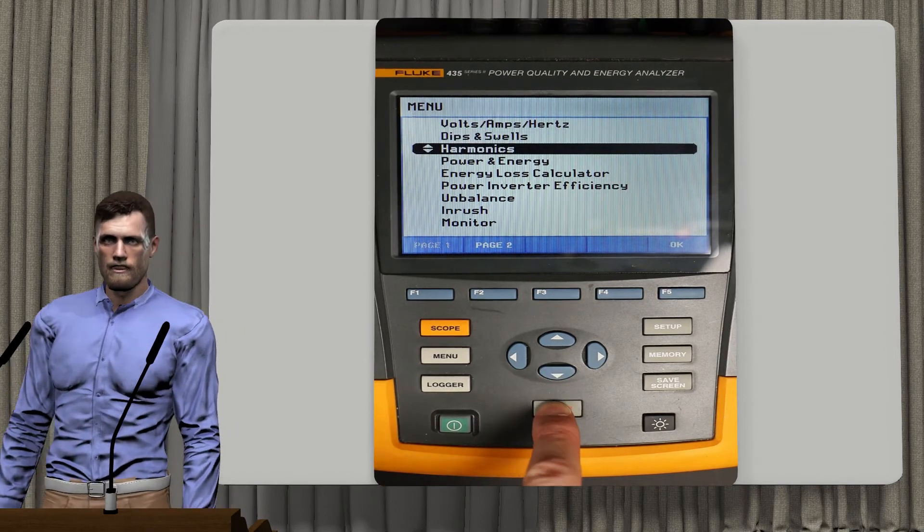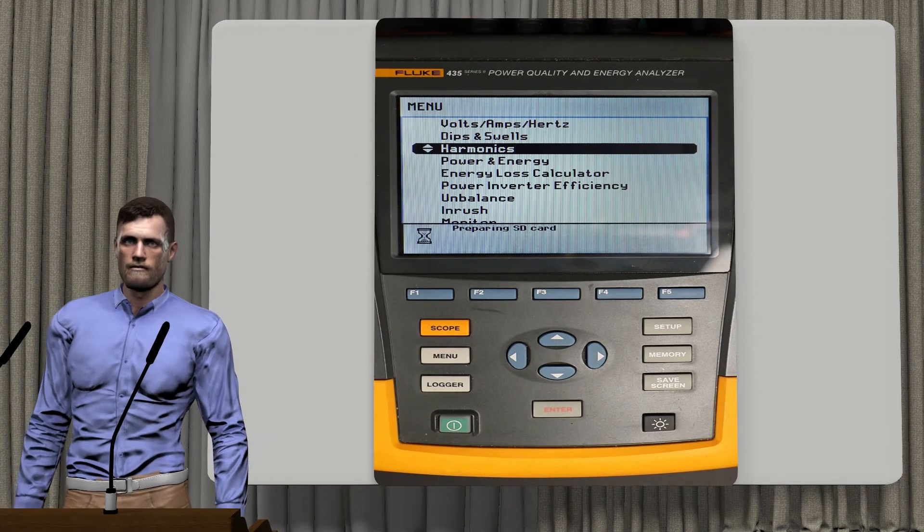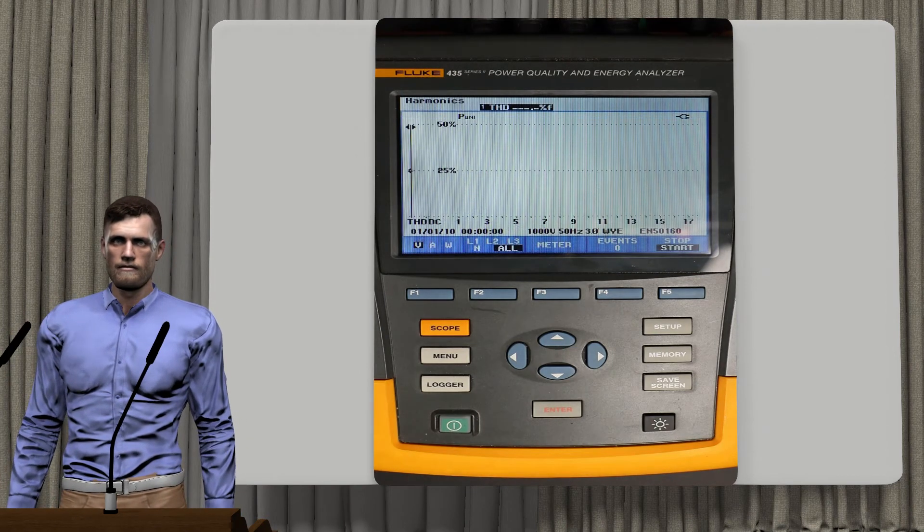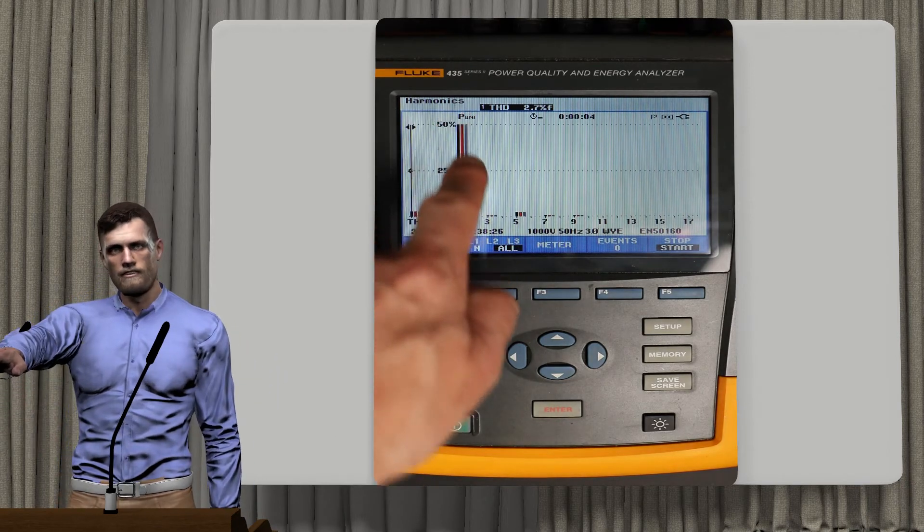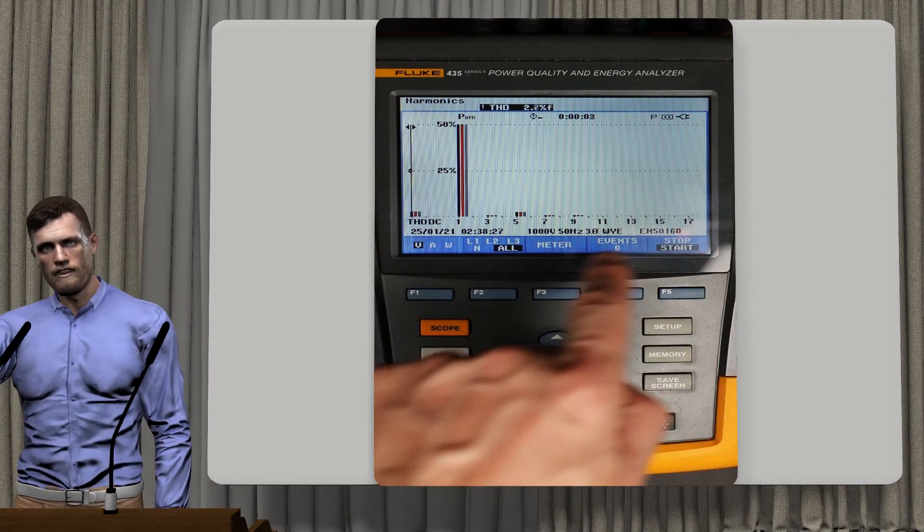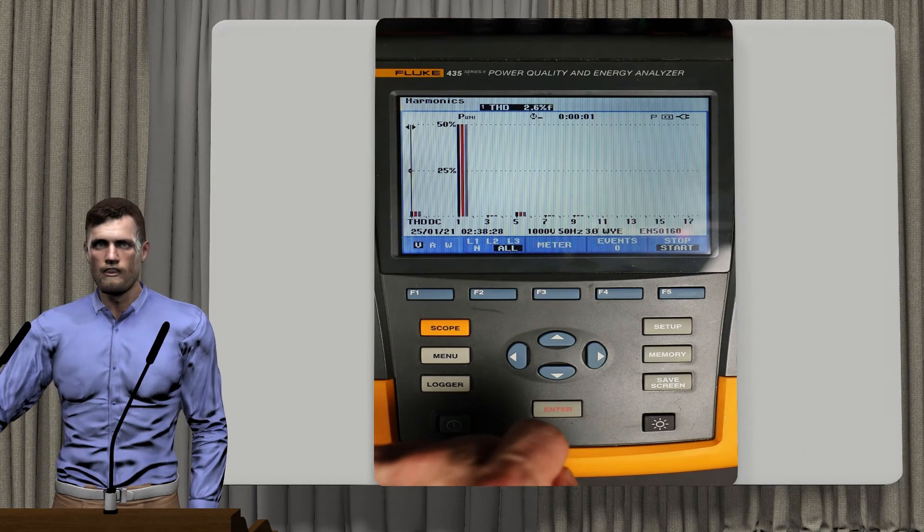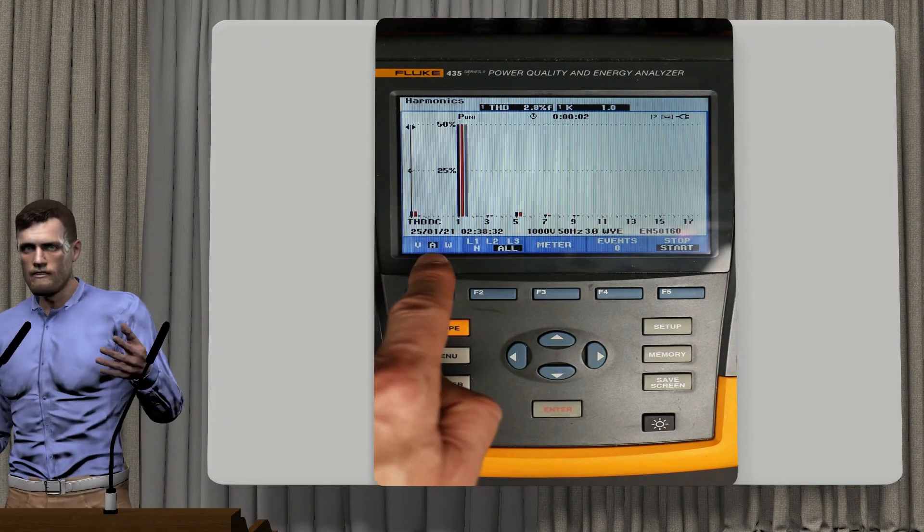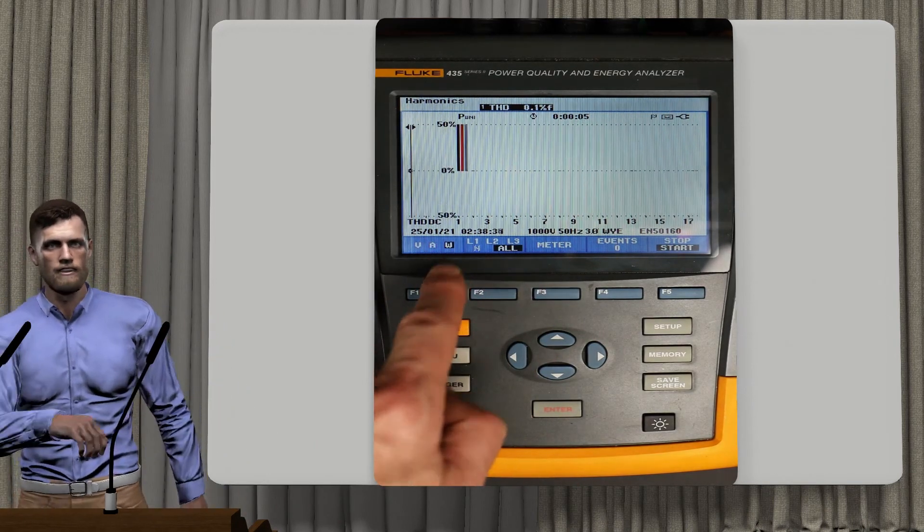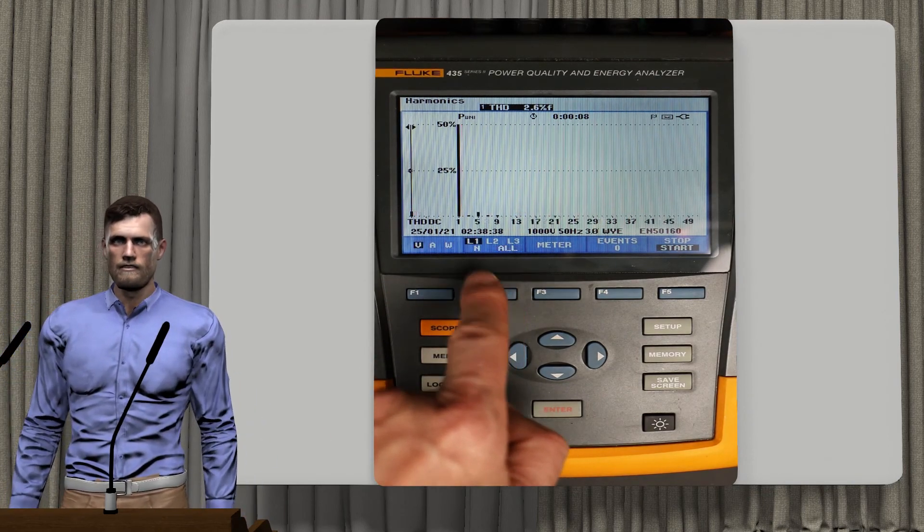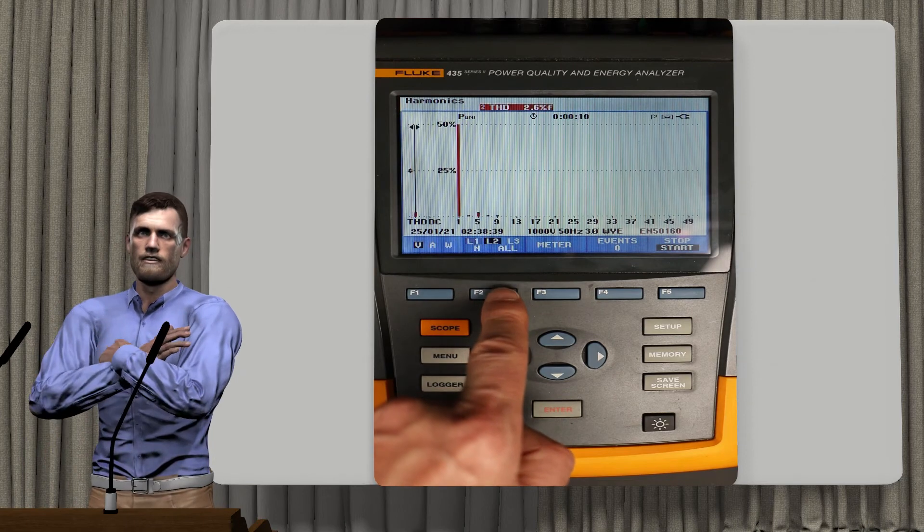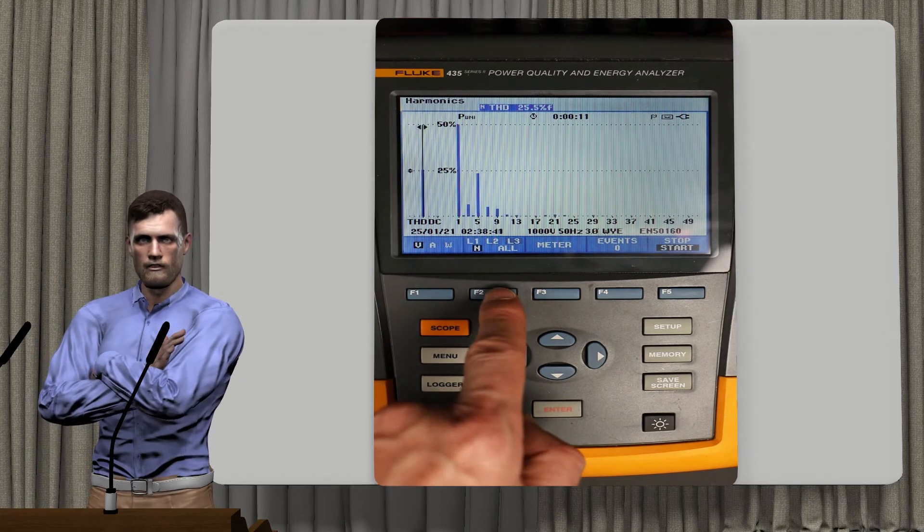As we can see, as soon as we enter the harmonics menu, the typical bar graph appears, where on the horizontal axis we have the order of the harmonic, and on the vertical axis the magnitude of it. This equipment can analyze up to the 50th harmonic. With the F1 button we can select between voltage, current or power harmonics. With F2 we can select if we want to visualize the three phases, or each phase individually, each one with a different color.